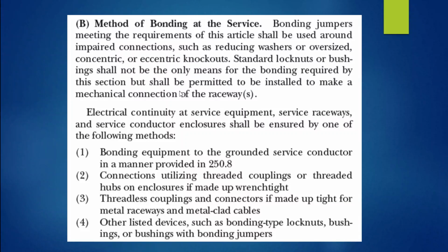Again, if it's rigid, you want to hold the raceway in place, you have to connect it to the box. Yes, locknut to be there. But opposite the locknut, we want to have some other method to do that. We can't rely on a standard locknut. That's only for mechanical purposes. Now, electrical continuity at service equipment, service raceways, and service conductor enclosures shall be ensured by one or more of the following. Here we have bonding equipment to the grounded service conductor in a manner provided in 250.8, meaning threaded entries, all those types of things that are listed in 250.8 are considered acceptable.